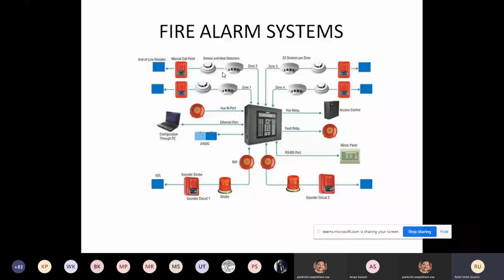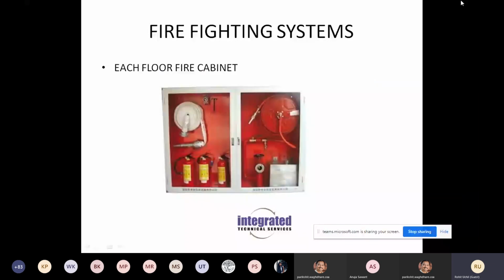In addition to this, the landing valves in this cabinet, another important part of the firefighting system is the sprinkler system, which is nothing but a network of pipes which have sprinkler bulbs. They're called sprinkler bulbs, and these bulbs burst at certain set temperatures, maybe 58 degrees or 64 degrees or 120 degrees, depending upon the environment.